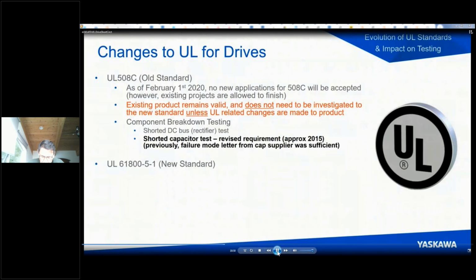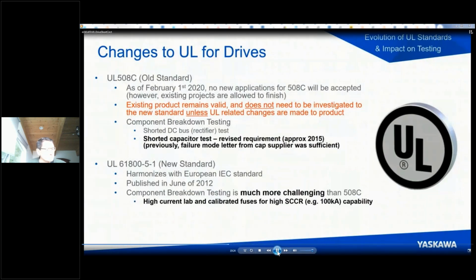Okay. So again, though, now the way of the future is really this new standard, which is 61800-5-1. That actually might look a little bit familiar to you, that number, because there is also a European IEC standard that it's harmonized with. So you'll see an IEC standard with that number, and you'll see the UL standard. And they share a lot of the same requirements, but they are not exactly the same. So this was actually published all the way back in 2012.